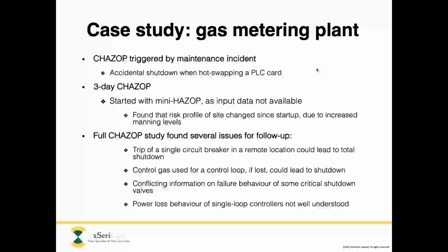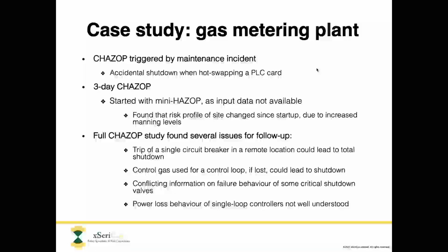There were quite a number of other issues that we found as well. And some of them were that the system was actually not as well understood. They were lacking some information on how the system would behave in certain upset scenarios. So all in all, very interesting, and I think a very worthwhile CHAZOP study there for really relatively little cost.